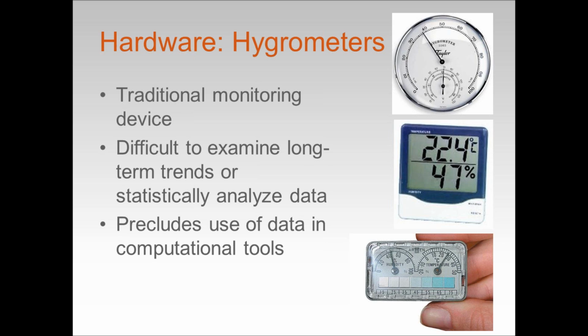Okay. Hygrometers are devices that measure humidity, and thermohygrometers will measure temperature and relative humidity. They're low-tech options, but they still have a place for certain applications. There are analog versions, like this dial type, seen in the top right corner, or digital versions like the ones shown in the middle. The example on the bottom is called the R10, and you see that it has a dial for humidity, a dial for temperature, and then one of those humidity strips that Priscilla mentioned, ranging from pink to blue at the bottom, and that's designed to be a redundant check on the humidity so that you know when they need to be recalibrated.